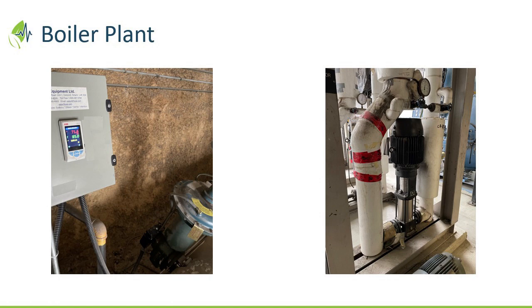But in addition to that, every economizer should have a bypass orifice, again, to keep them wet. In Brent's case, he's got 4 boilers, 4 economizers, and so all those economizers are always seeing feed water bleeding past them, whether they're running or not. So why send hot deaerated water through a heat exchanger in an offline boiler? So now we're taking heat energy out of the economizer if you're not putting it in, and you're losing energy. Plus, you're just diverting unnecessary flow. So we're looking to address that with an on-off valve that'll be commanded by the boiler. So you cannot run the boiler if you don't have flow in the economizer.